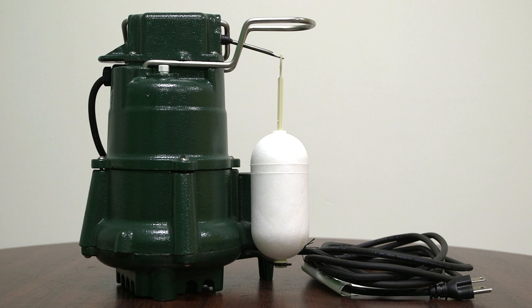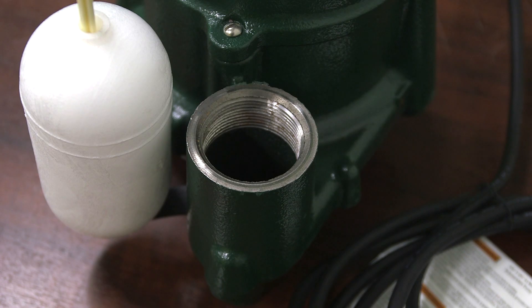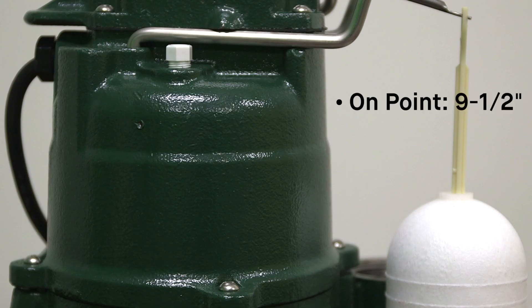The maximum temperature for effluent or dewatering is 130 degrees Fahrenheit. It also passes ½ inch spherical solids and has a 1.5 inch NPT discharge. It has an on point of 9.5 inches and an off point of 3 inches.